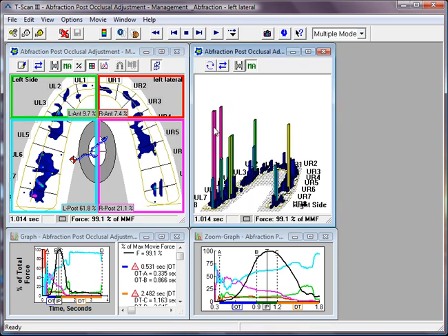And also what you'll see is that there are some purple colours. What purple means is that those particular sensor cells were maxed out, so they went too red, and then there was an increasing force on them of which the sensor could not read the increasing force, so it just indicates to you that it reached its maximum limit of recording. So that's fine as long as you don't have too many of them.